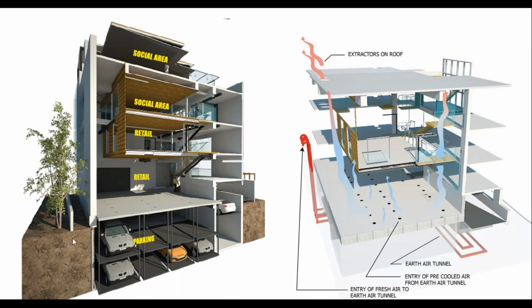Because it's a very tight site, we had just about 5 or 6 feet in the setback. We got fresh air from the side into the earth air tunnel, then into the air handling unit with a BMS to check if further cooling was needed. Otherwise it would just be filtered and go back to the basement ceiling, from where diffusers send cool air to all the floor diffusers.